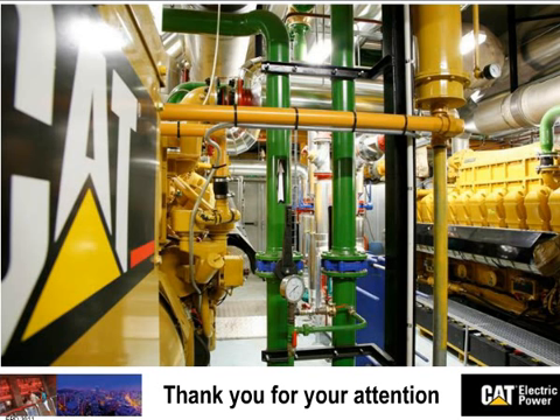Here's another question related to your discussion of greenhouses. Is it practical to use a G3412? And for those on the line maybe not familiar with our product ratings, that would be about a 350, 450 kW size electric genset. Is it practical to use a G3412 and an SCR to provide carbon dioxide for greenhouses? Does this make sense in a cost per kilowatt hour or cost per kilowatt basis?